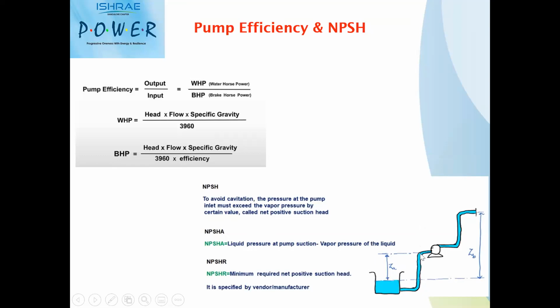You can get the formula in your books, reference books, or you can search on Google also. You can see the formula available for NPSH calculation, which is very simple. The atmospheric pressure minus the vertical height minus the frictional losses on the suction side of the pump will give you the net positive suction head available at the site.